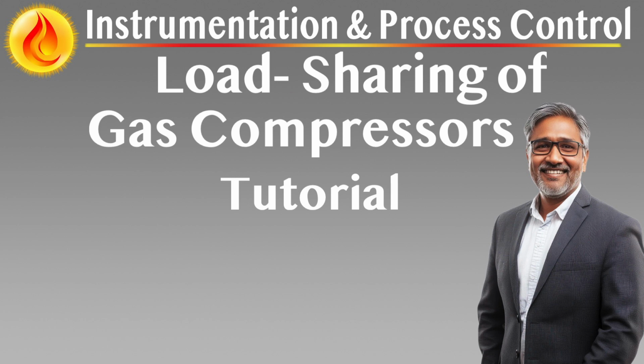Flow redistribution. Without process disruption, no change is made to the set points of other control loops, e.g., load sharing or station control. The adjustment occurs solely in the valve response timing, not in the target values. This avoids conflicting signals and preserves the integrity of higher-level control logic.